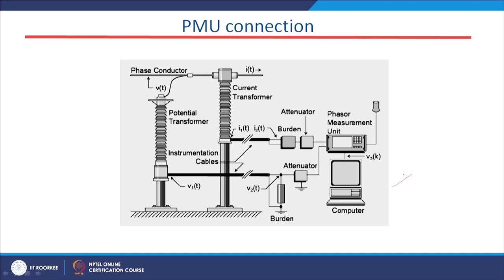A PMU connection snapshot shows the phase conductor, potential transformer, and current transformer. The current transformer is connected to the PMU terminal through a burden, and the instrument transformer is connected through an attenuator to the voltage terminal of the PMU. A computer is connected to the PMU interface to analyze the voltage and current phasor data; the PMU can also record frequency and rate of change of frequency if properly customized.